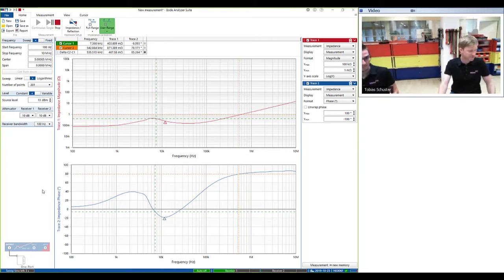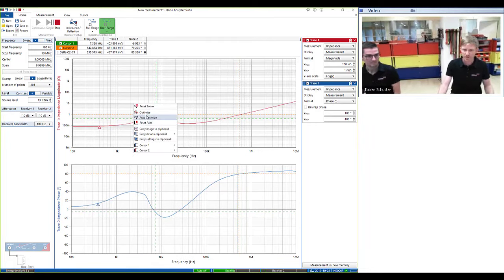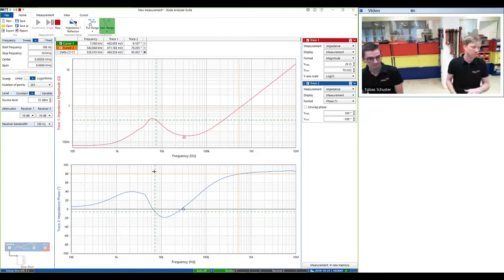So the cable that we use is not so nice, and we already see the drawback of the one-port method. The problem of the one-port method is that it's a two-wire connection, so it's sensitive to contact resistance, and the impedance that we are measuring here is below 100 milliohms in some points. So the contact resistance of bad connections can corrupt the measurement, but now the measurement looks nice, and we're gonna use the phase margin calculation to calculate the phase margin.